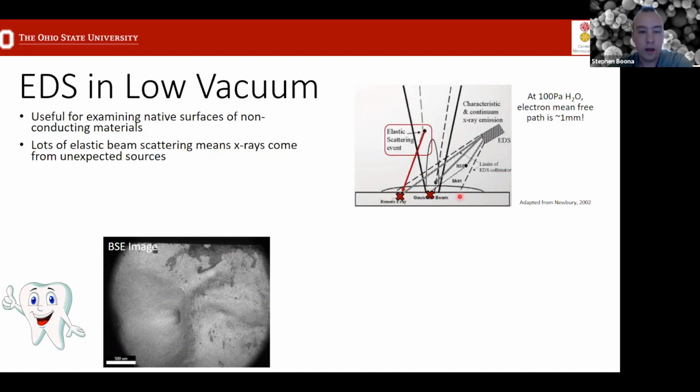And so the software thinks that the beam is here, and it's correlating that with an X-ray that was detected after being generated actually somewhere over here. That area is described by this term they call a skirt. Depending on the parameters you use for your data collection, this can potentially be millimeters away, so that is outside the field of view of the sample in this image.